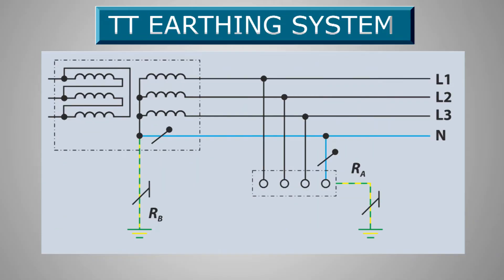Let's look at the TT earthing system as an example. In this earthing system, connection to the supply source is directly connected to earth, and the load end or installation metalwork is also directly connected to the earth. Therefore, in case of an overhead line, the mass of the earth will be the return path for the line. The neutral and earthing conductor must be separated through the installation, because the power distributor doesn't provide a supply neutral or protective conductor for the connection to the consumer.